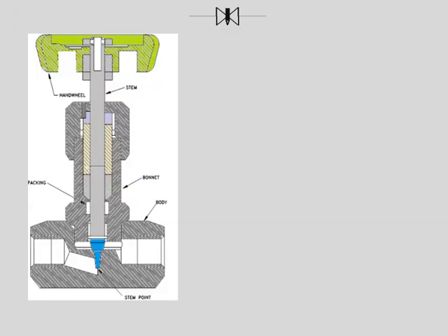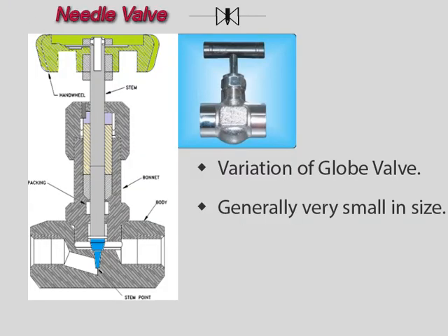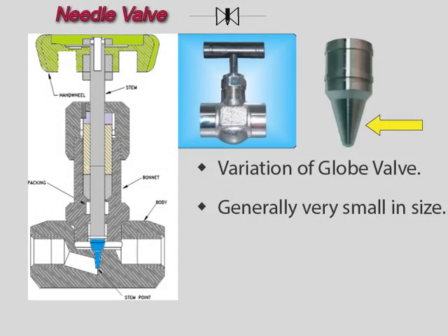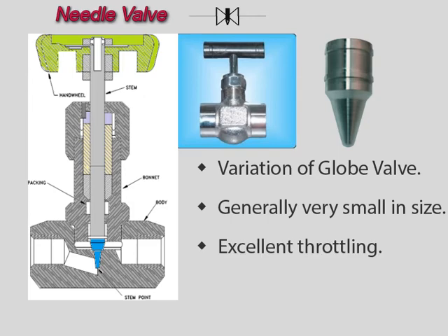A needle valve is a variation of the globe valve design used to make relatively fine adjustments in the amount of fluid flow. The distinguishing characteristic of a needle valve is the long, tapered, needle-like point on the end of the valve stem — the needle acts like a disc. The advantage of a needle valve is the excellent throttling characteristic and fine flow adjustments that can be made. The disadvantage is the extremely large amount of head loss that occurs across the valve.